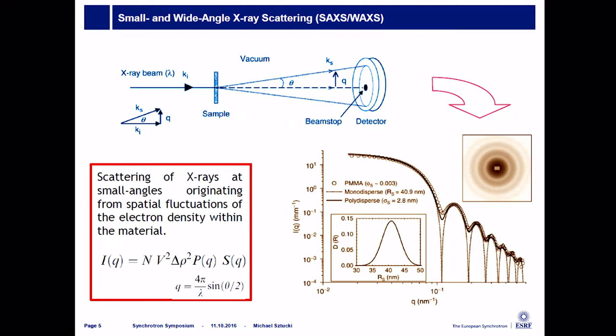How does small angle X-ray scattering work? Actually, it's a very simple technique. You have a beam, you just put your sample into this beam. In the forward direction, you place a 2D detector — either a CCD detector or a pixel detector — and there you register a 2D pattern of the scattering signal. Unfortunately, this is not a direct imaging technique, so you have scattering intensity in reciprocal space and you have to interpret your data later on.